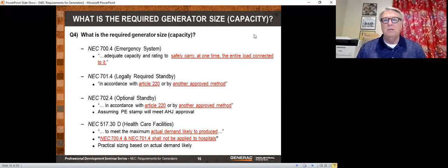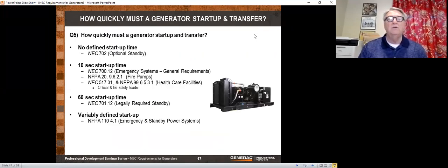But it also says by another approved method. What does approved mean? Well, that means that your inspector is okay with it. And then, of course, there's the healthcare facilities. And they make the most sense of all because they say you need to size it to meet the maximum actual demand likely to be produced. Well, gee, now that one actually makes sense. I wish they would have said that same thing on the others.